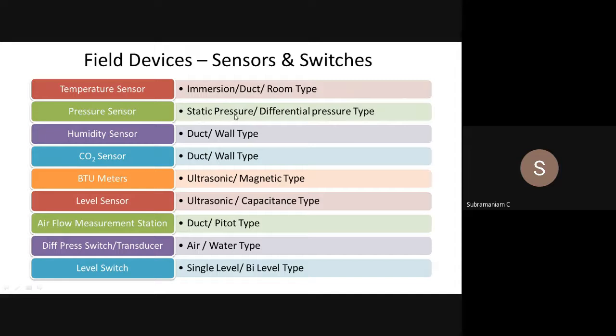Pressure transducer, it can be a static pressure sensor, differential water pressure sensor, duct static pressure sensor, or a pressure transducer across your HEPA filter, or a differential water pressure transducer for controlling your secondary pump VFD speed, where I am putting it across the chilled water supply header and return header. Humidity sensor again will give you either 0 to 10 volt DC or 4 to 20 milliamps. CO2 sensor, BTU meters. So that will give over M-Bus or Modbus or BACnet. Level sensor, or I can have a level switch.